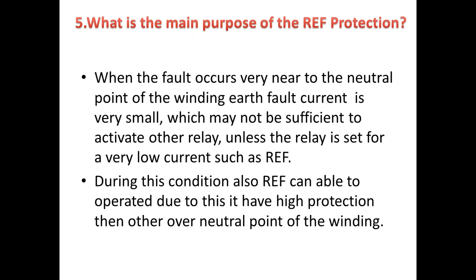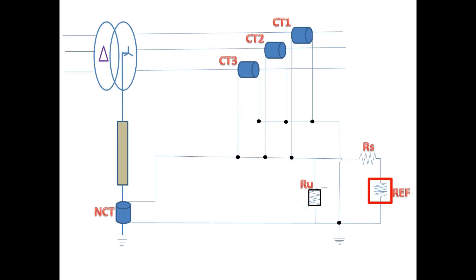Fifth question: what is the main purpose of REF protection? When the fault occurs very near to the neutral point of the winding, the earth fault current is very very small, which is not sufficient to activate other protection unless the relay setting is set at a very low value. During this condition, REF is able to perform very well over other protection near the neutral point of the winding.